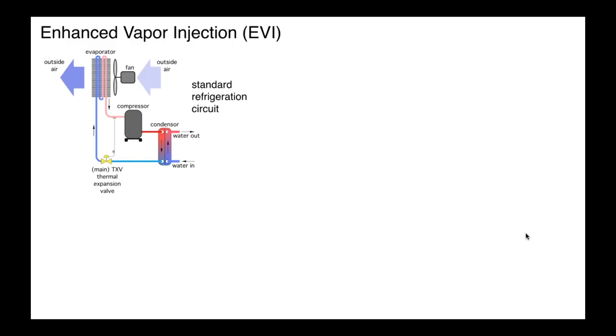And to show you that, we'll start with a non-EVI system. This is a standard refrigeration circuit where in an air-to-water heat pump, we've got that outdoor coil, and in the heating mode operation, again, we're using the outdoor coil and the fans to absorb low-grade heat from the outside air. We've got the compressor, and we're sending our hot gas from the compressor into a heat exchanger, and we're extracting that heat with a stream of water, and then we are taking the condensed refrigerant through a thermal expansion valve, lowering its pressure, which causes the temperature to drop, and then we go back and repeat the cycle. Again, a very basic four major component refrigeration cycle.